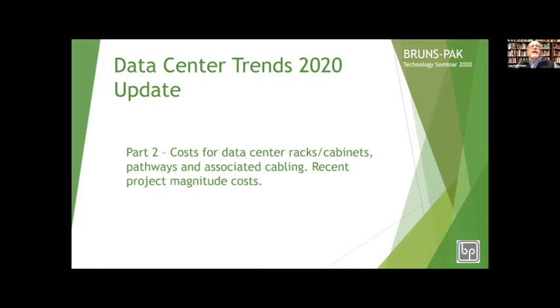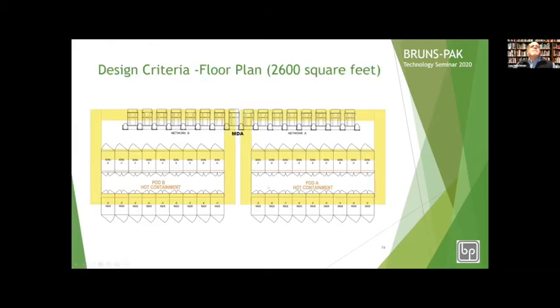Part two is an interesting analysis — the cost for data center racks, cabinets, pathways, and associated cabling with recent, September project magnitude costs. These costs were actually bid, so this is not a guess. The data center we did this analysis for has 36 IT racks and 16 network racks with overhead two-tier tray, hot containment, Pod A, Pod B, Network B, Network A, and the MDA. It's a 2,600 square foot data center.